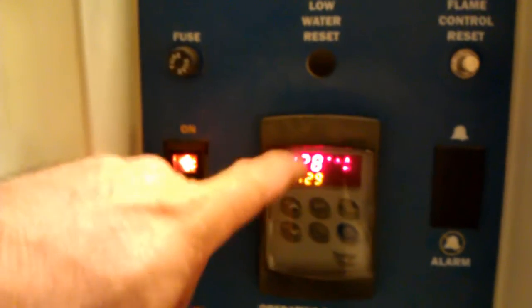Outlet water temperature. The top one, I just replaced that sensor right here. It was actually bad. But you'll see the heat rise once it ignites.